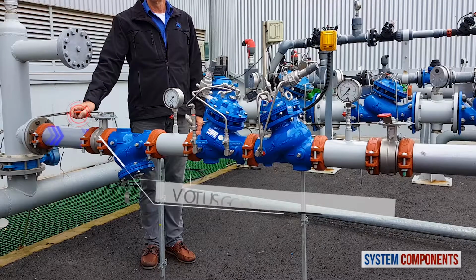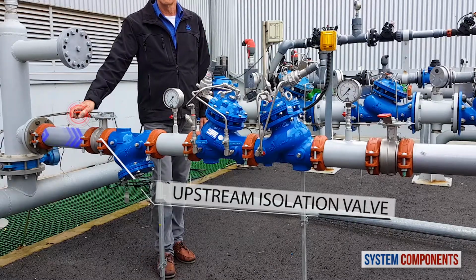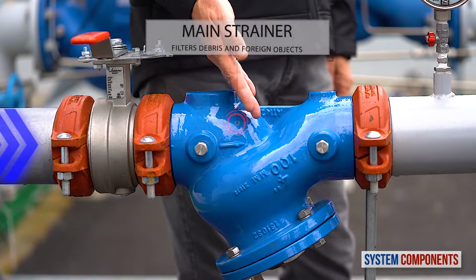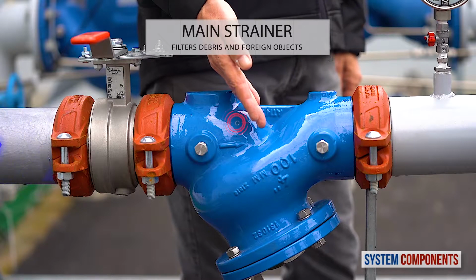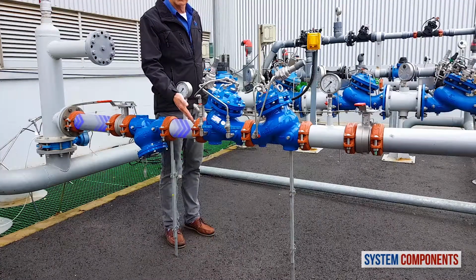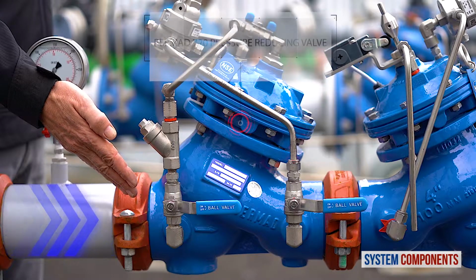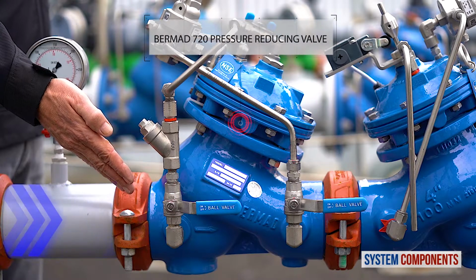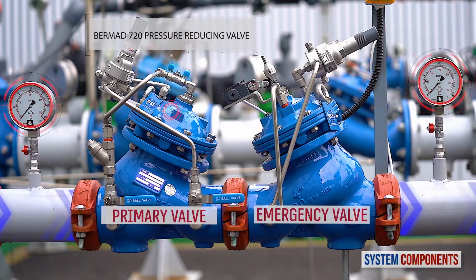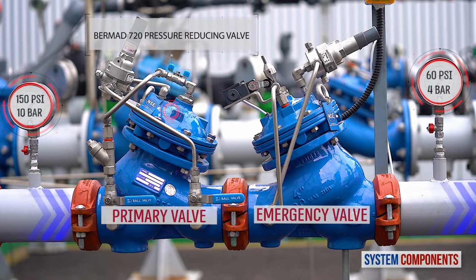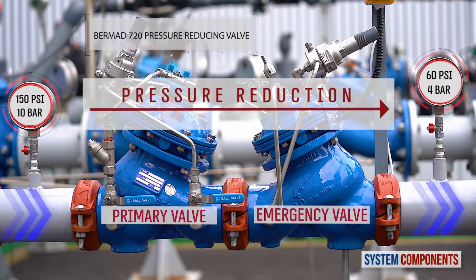When the upstream isolation valve is opened, water first encounters the main strainer, trapping any debris or foreign objects. The water then enters the primary BERMAD 720 pilot-operated reducing valve. This valve is calibrated using a pilot to reduce the upstream pressure to the design pressure value for the consumer line.